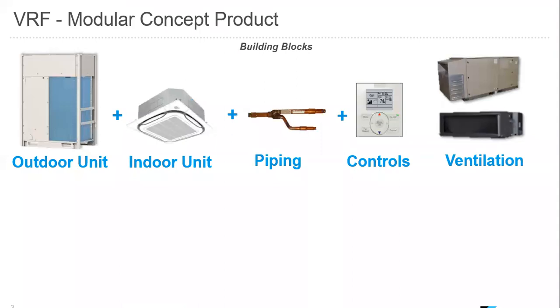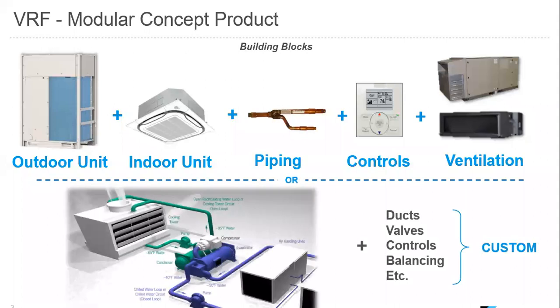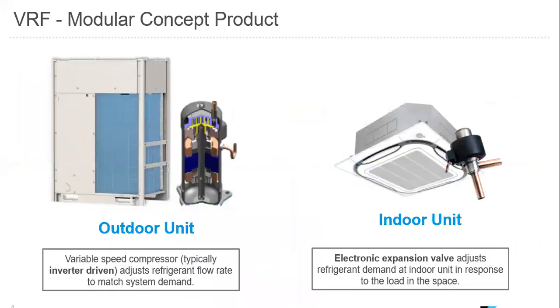VRF is a very modular product. The main components are outdoor unit, indoor unit, piping, controls, and ventilation. A very simple system when you think about these 5 components. Traditionally, VRF has grown very rapidly over the last several years. We started out being known as the chiller killer, and that's why I show an image of a chiller below. You'll see that a chiller has a lot of complex components. We have ducts, valves, controls, balancing, and VRF is just a lot more simple and provides comfort cooling, energy efficiency, and easy maintenance.